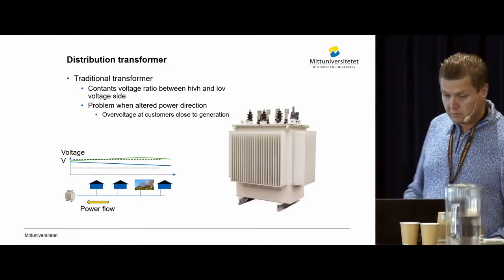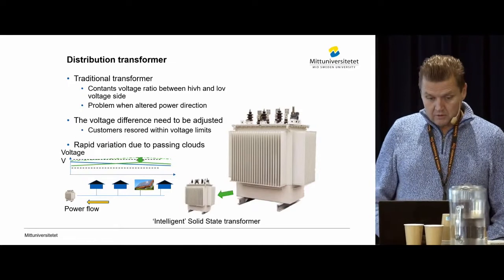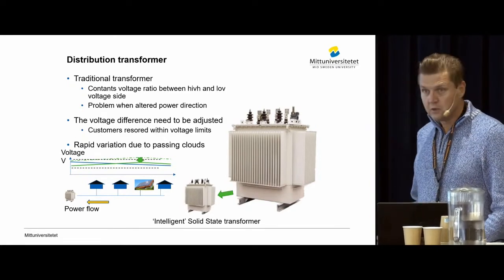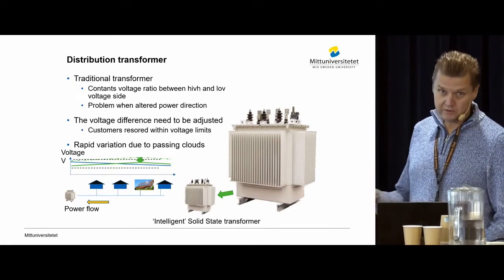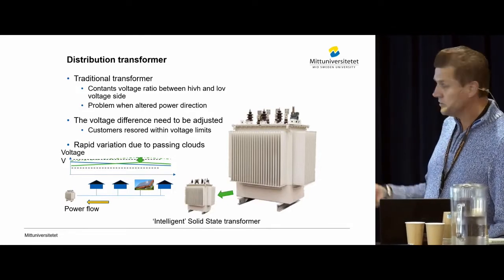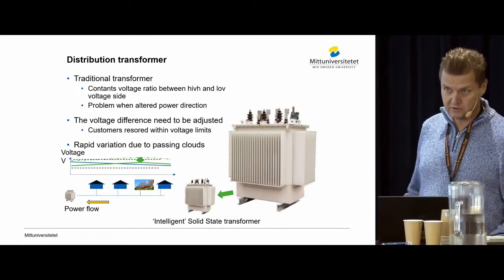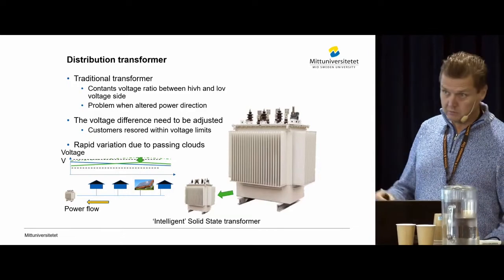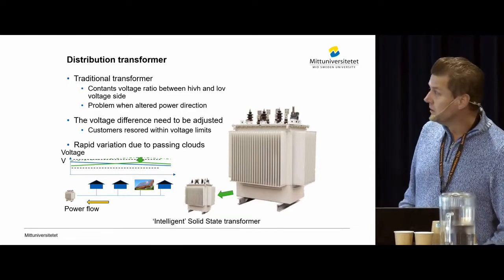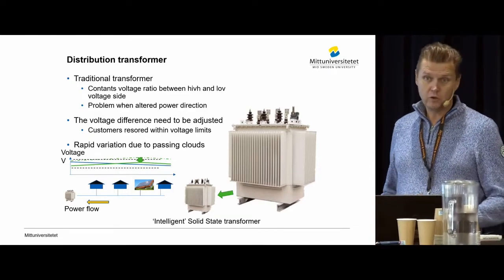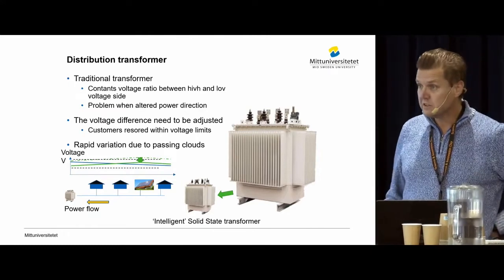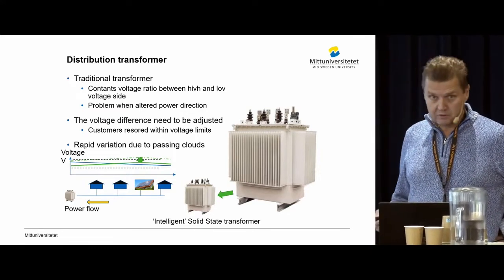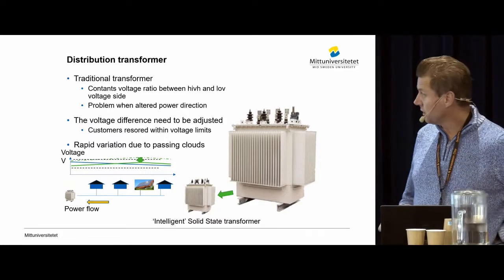So you need to do some modification there. What you could do, dynamically or statically, is change the transformer with a tap changer, either used manually or done dynamically for slow variations. But you don't have that remote control in that many places far out in the grid.